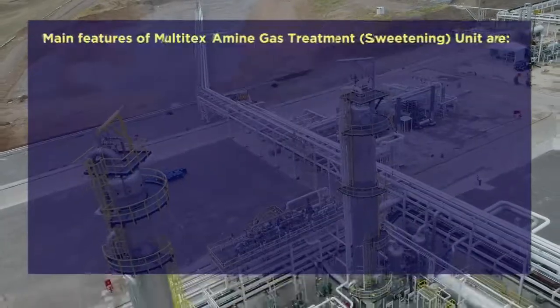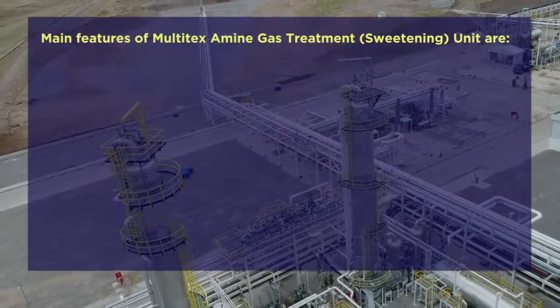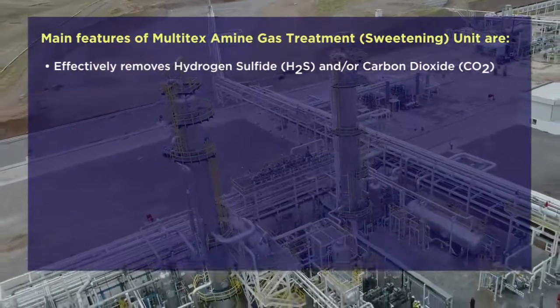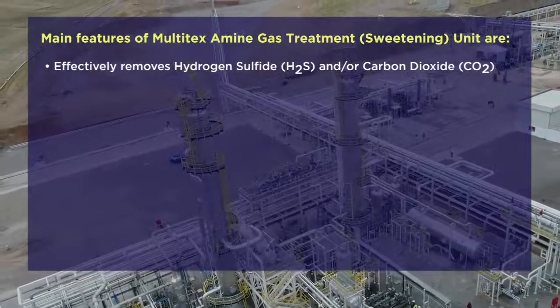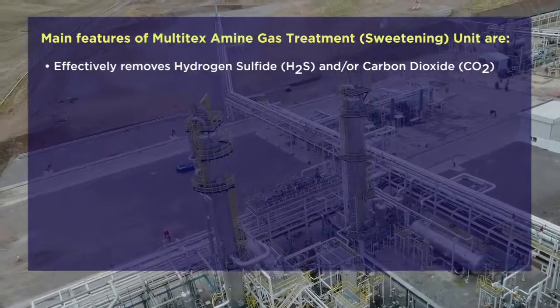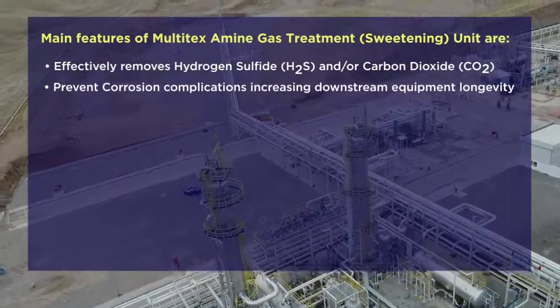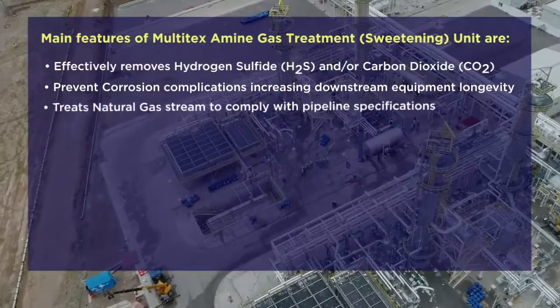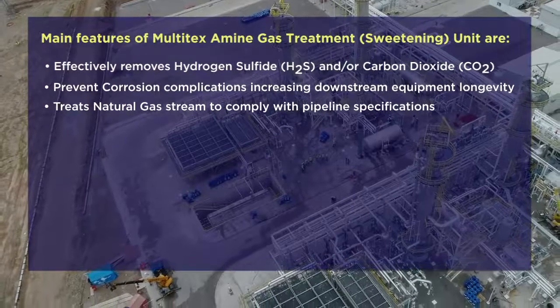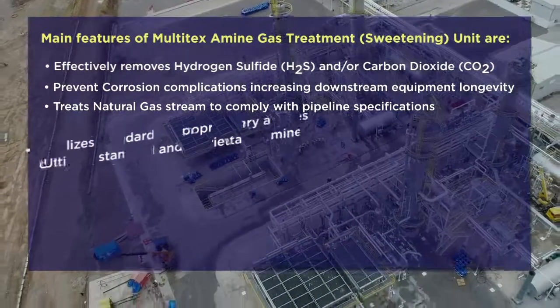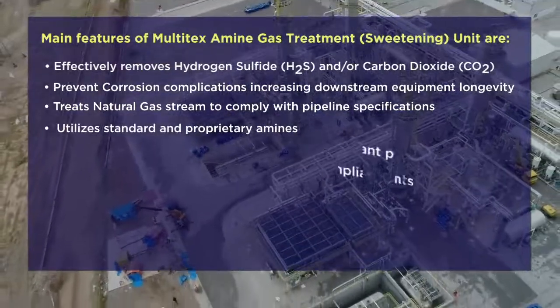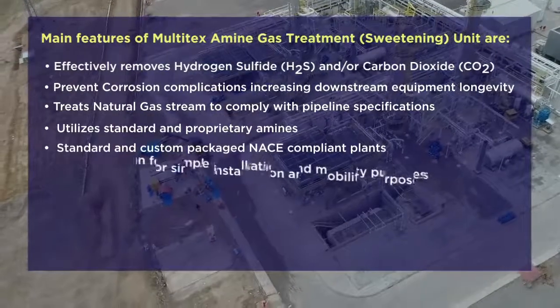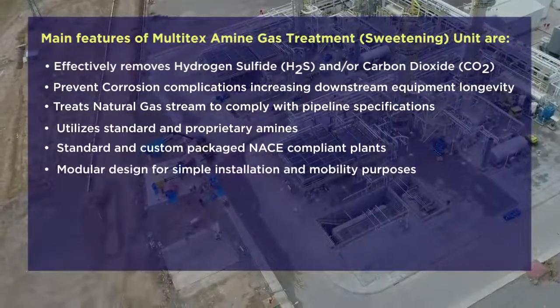The main features of Multitex amine gas treatment sweetening unit are: it effectively removes hydrogen sulfide and/or carbon dioxide; prevents corrosion complications, increasing downstream equipment longevity; treats natural gas streams to comply with pipeline specifications; and utilizes standard and proprietary amines with standard and custom package NACE-compliant plants, featuring modular design for simple installation and mobility.